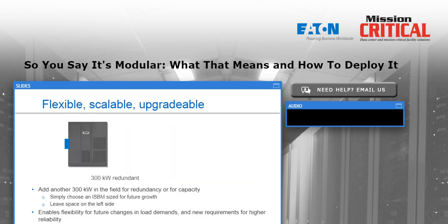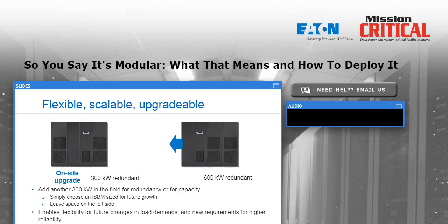This is the kind of thing you would want to look for in any modular, scalable, large UPS system. Now, this next slide shows the addition of an extra module on the left-hand end. There are lots of different ways to accommodate growth here, but most of them do require, first of all, that the client go ahead and install the premises wiring sized as large as this UPS could eventually possibly be. So if I buy this UPS as a 300 and end up growing it to a 600, I wouldn't want to change the premises wiring at that point. I would already want to have the proper conduit and wire in place and the proper upstream breaker protection, etc. I may never need that capacity in the premises wiring, but if I do decide to expand that UPS, then that wiring is already done, significantly simplifying the process.